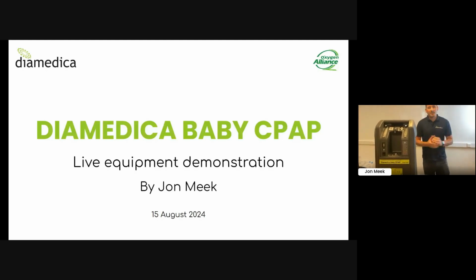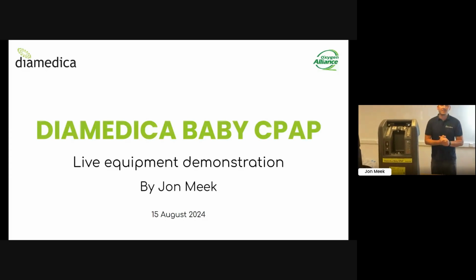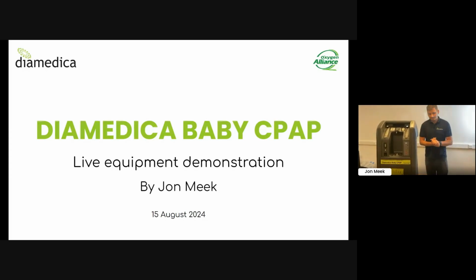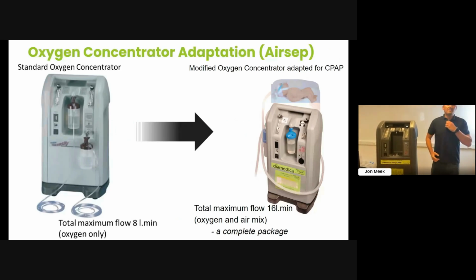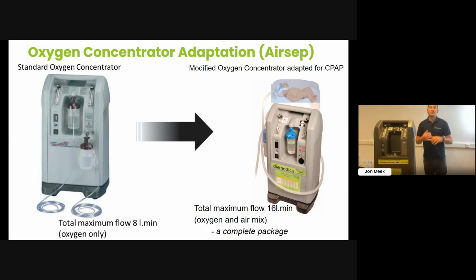So where did the Diamedica baby CPAP first begin? It was designed initially to provide safe bubble CPAP in areas that tended to not have the availability to provide safe CPAP. Oxygen supply, air supply was an issue, humidification, and all these factors which are so greatly needed in CPAP. Our first model, so we decided we needed to design a CPAP which produced its own oxygen, which eliminated the use of oxygen cylinders, which was heavily relied upon for most CPAPs, and also a safe control of bubble CPAP.